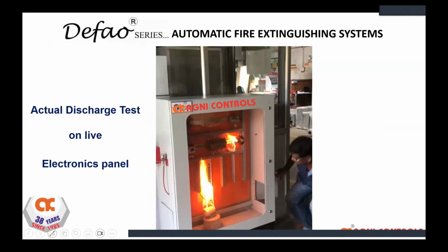So this is a small video for the benefit of others who have not seen automatic fire extinguishing systems. This is also known as the tubing system or sniper system, and many brand names call it using different names. It's an automatic fire extinguishing system. Here, this is a mock-up test panel. There is a fire detection tube which runs along the inside of the panel, and it finally comes out, and we have a pressure gauge connected to it. We have caused a fire at two different locations inside the same panel, and we are going to show that video.